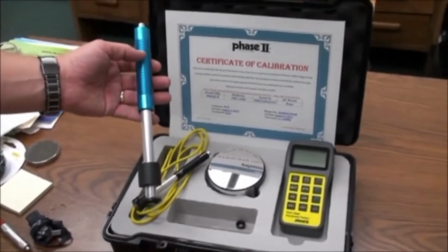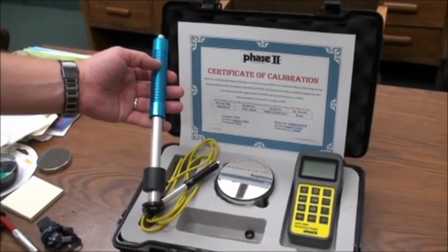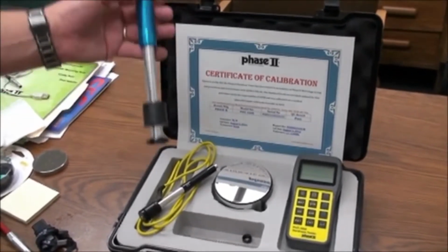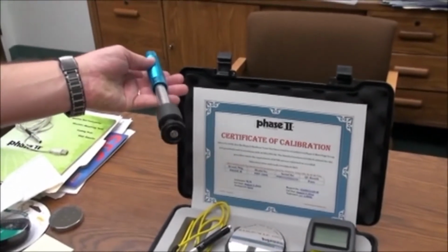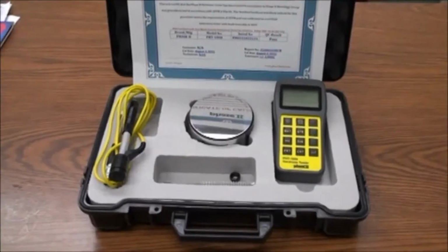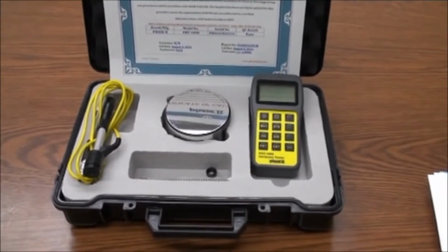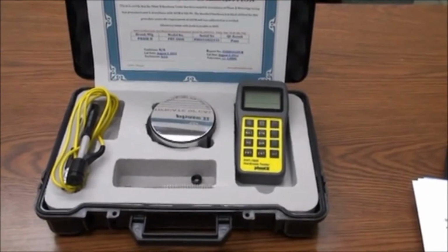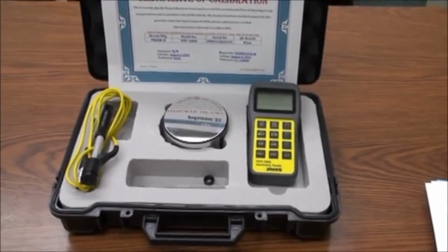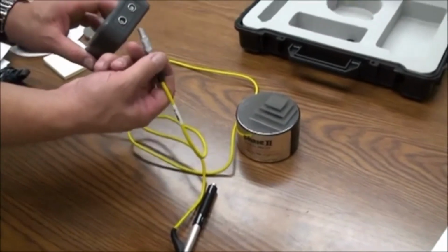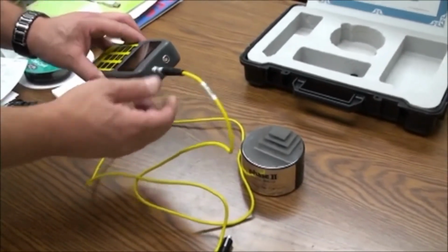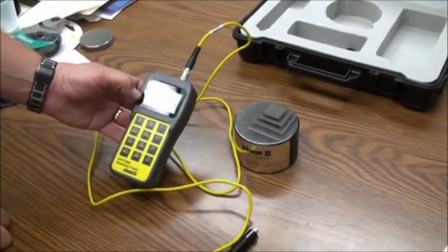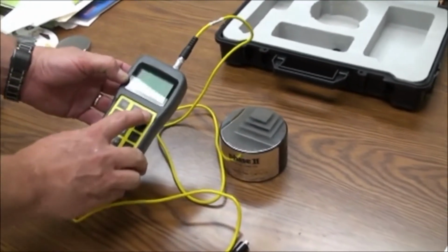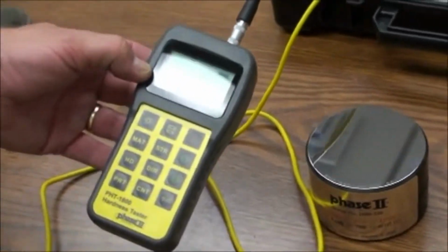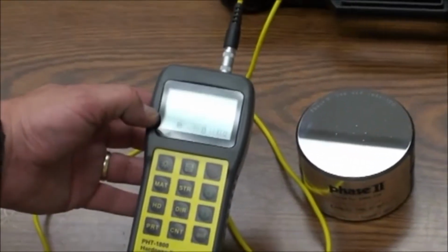The G probe is designed to test large, rough castings. It utilizes a 5mm ball, while all the other probes utilize a 3mm ball. Now let's move over to operation of the hardness tester and see how easy it is to utilize the different functions, taking tests, and obtaining results. To begin, insert the plug of the impact device into the correct socket on the tester. On the keypad, hit the power button to bring up your test screen. The main interface screen should be displayed.